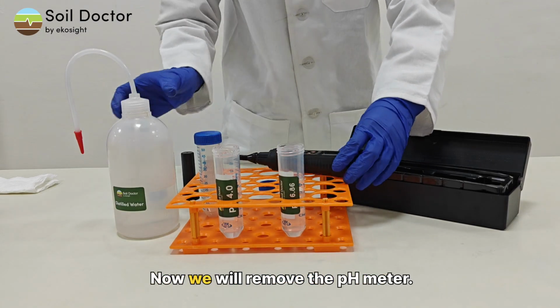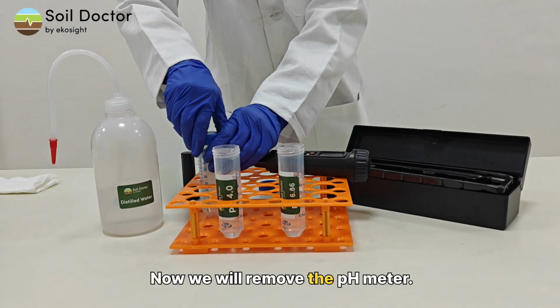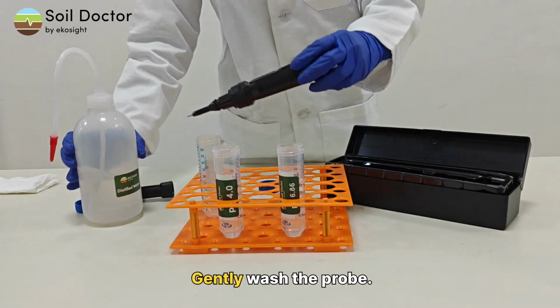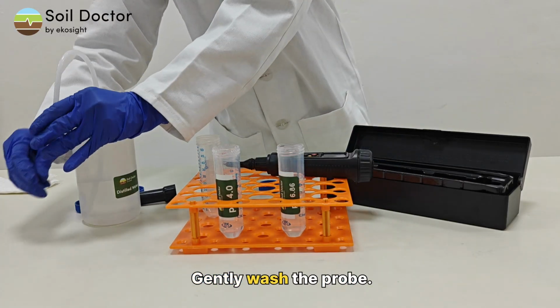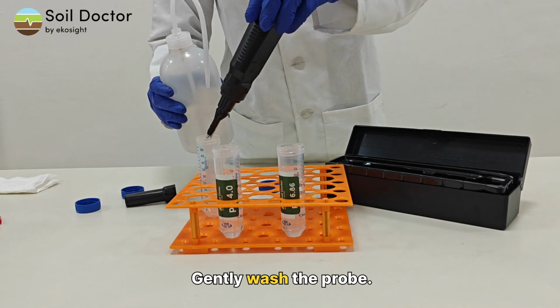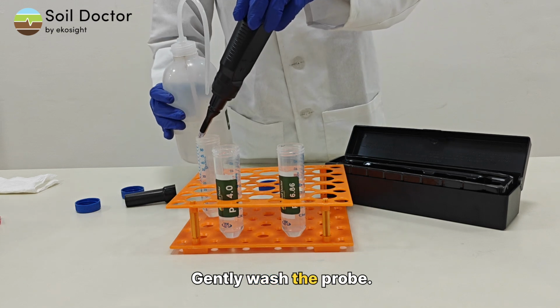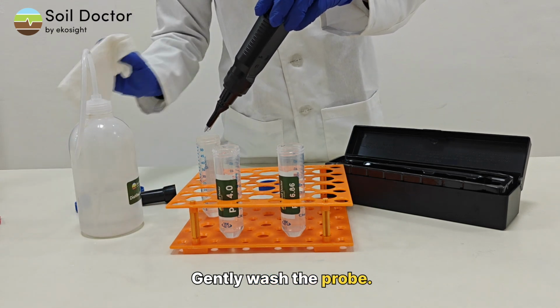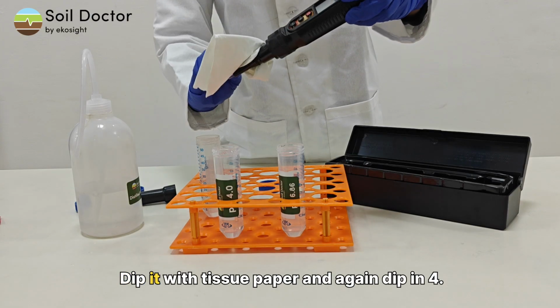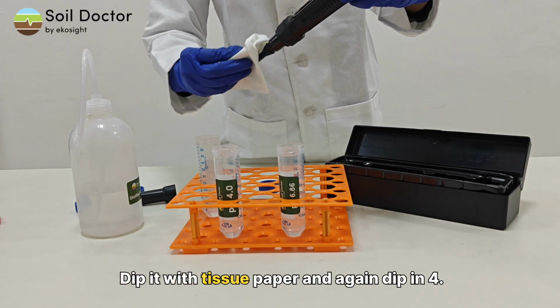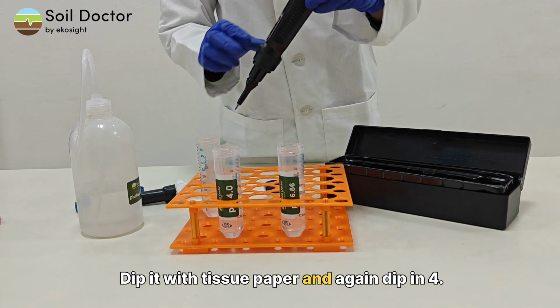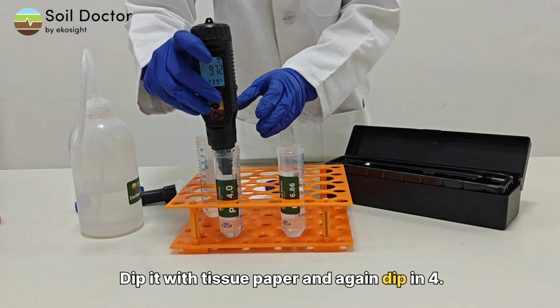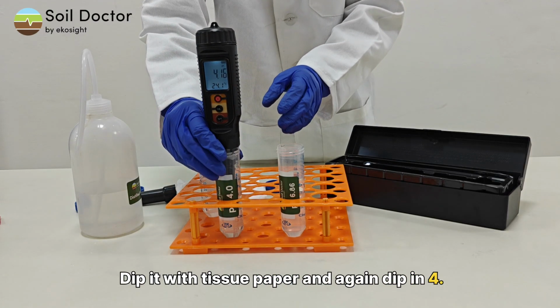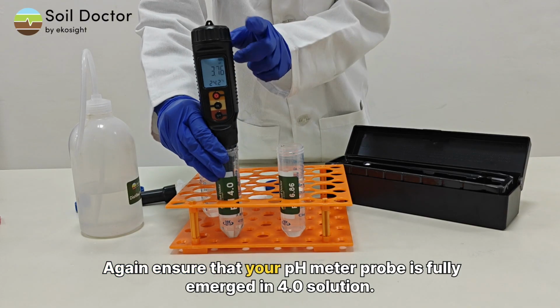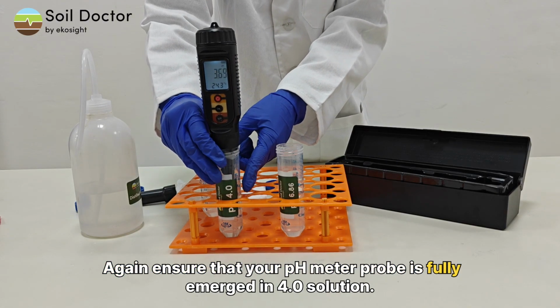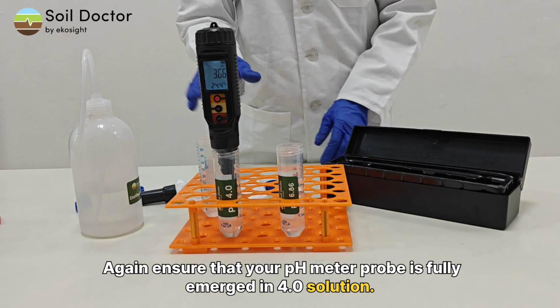Now we will remove the pH meter. Gently wash the probe. Wipe it with tissue paper. And again, dip in 4.0. Again ensure that your pH meter probe is fully immersed in the 4.0 solution. Wait a minute.